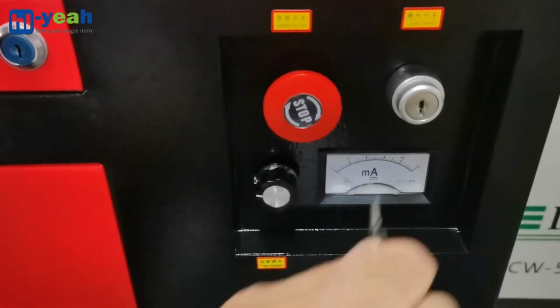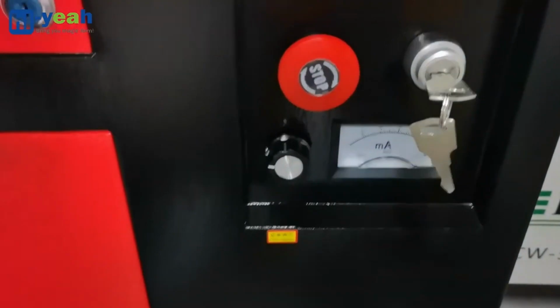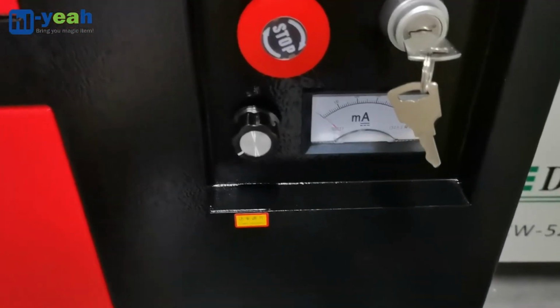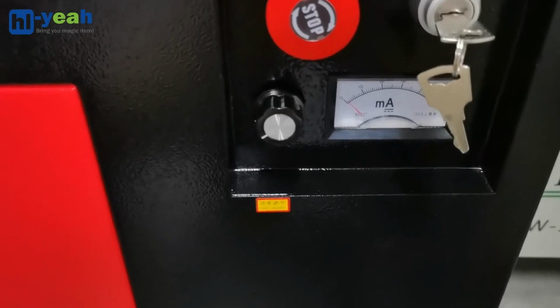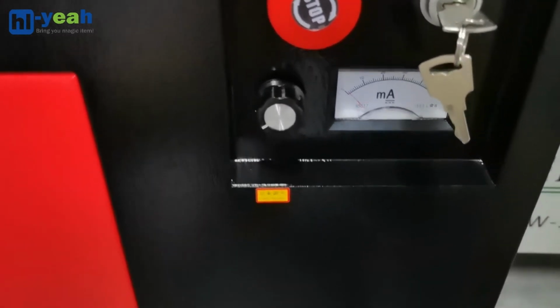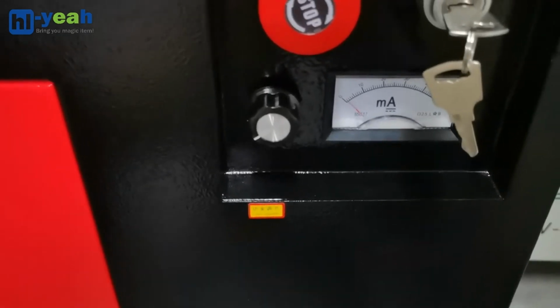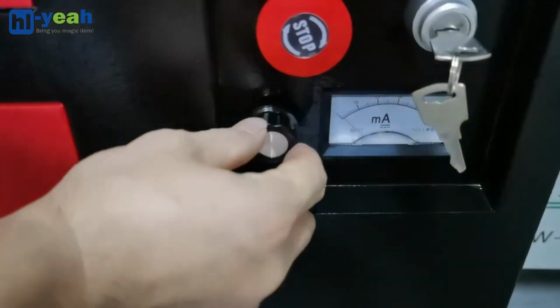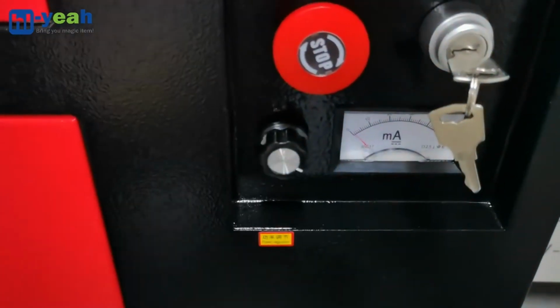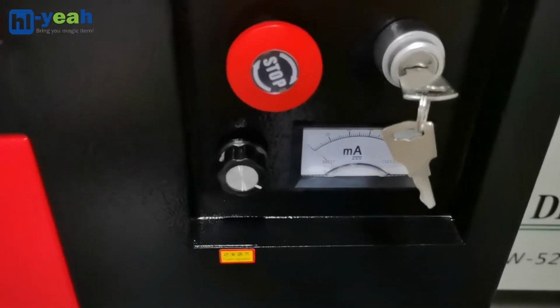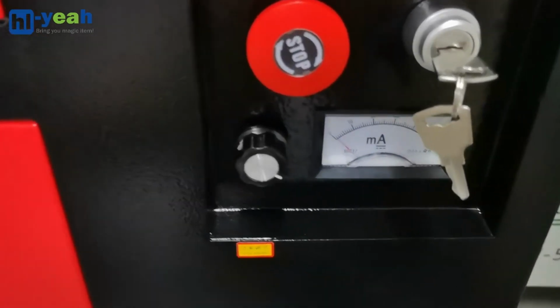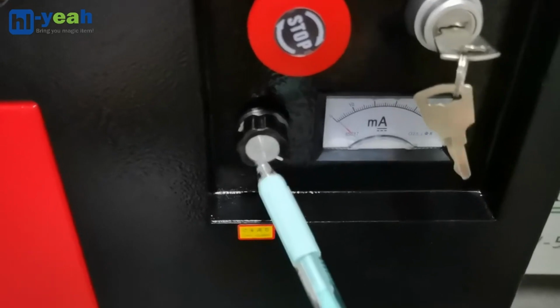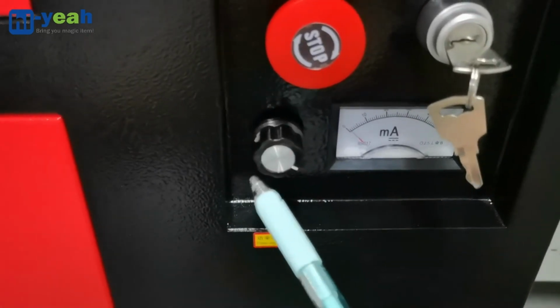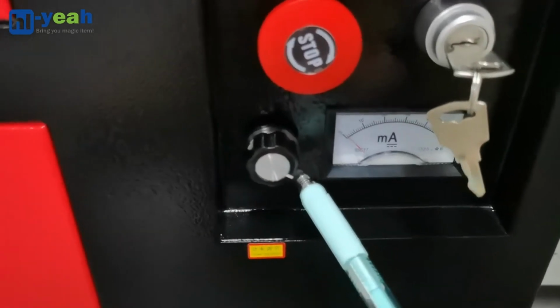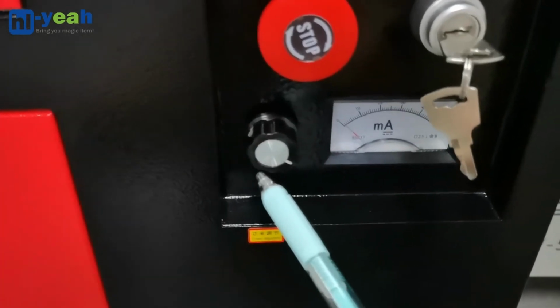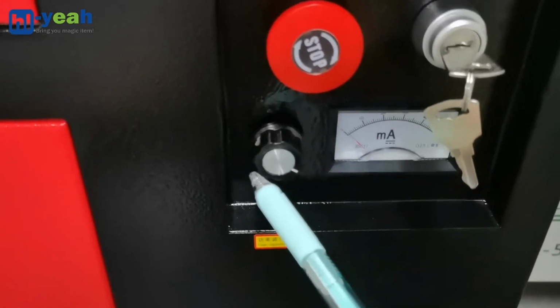I will insert the key and turn it on to the right. And the next thing, I will check the milliampere adjustment knob. I will turn it to the maximum this time. Sometimes you don't have the laser firing output because of the adjustment knob: you didn't turn it to the maximum but to the minimum, so you don't have the laser output.